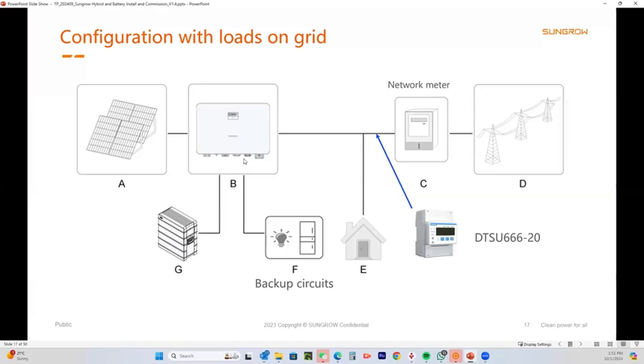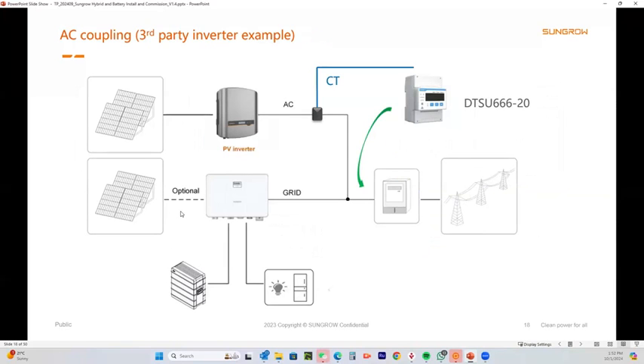This is DC coupling because you're charging the battery, which is DC, directly from the DC output of these panels. Obviously, the voltage is controlled, but when there's a surplus production, that is the system's producing more power than the loads are consuming, instead of that energy going out to the grid, getting the feed-in tariff, it will go directly to the battery and charge the battery. In this scenario, if you have panels connected, that is DC coupling, but you can, say, not connect panels and use the third-party system to charge the battery.